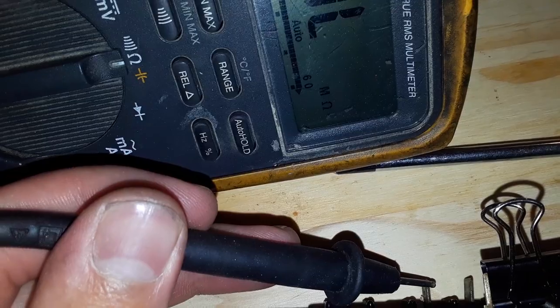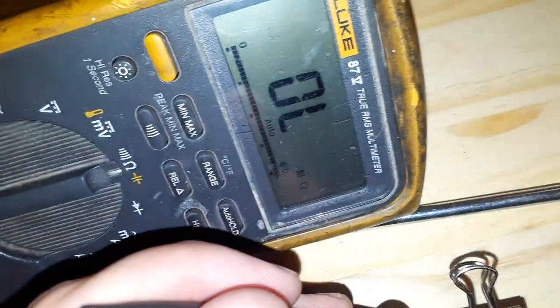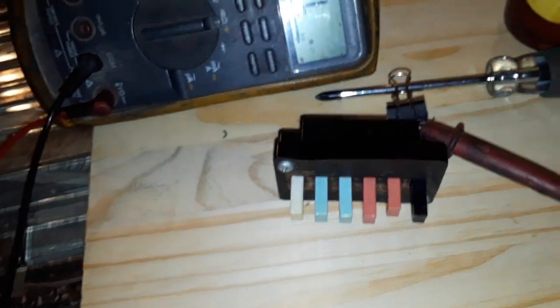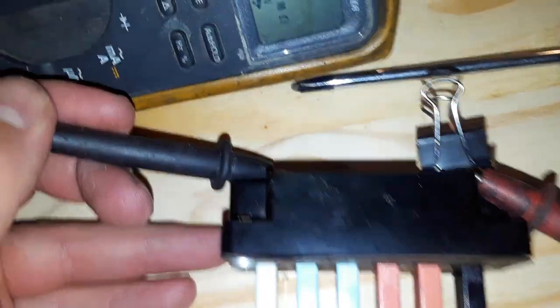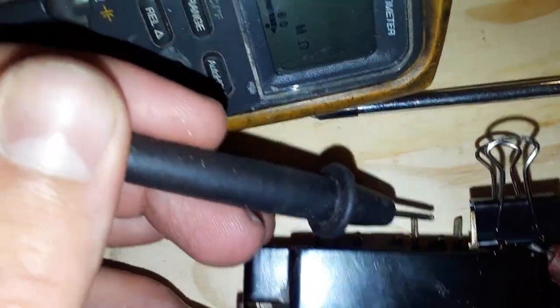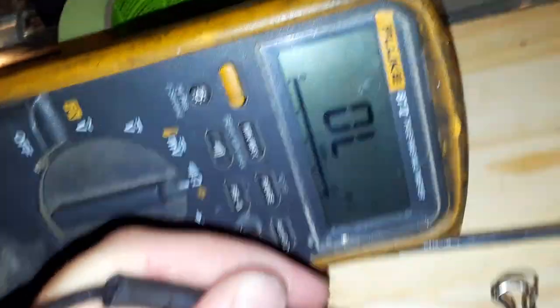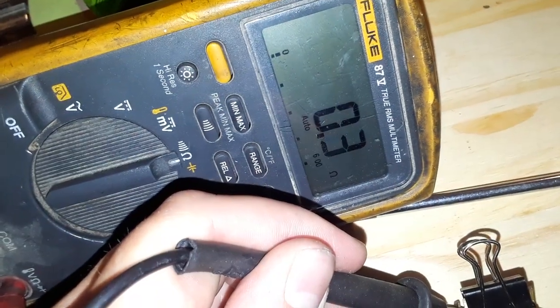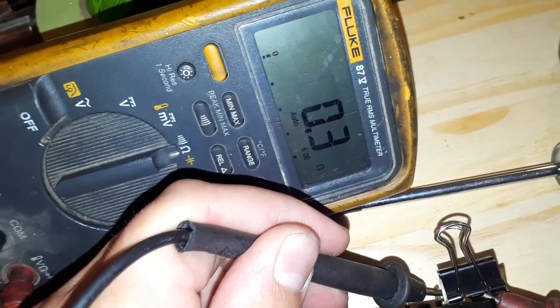So I should have no continuity on the compressor — it's off. And neither fan speed, high speed or low speed, should have anything. Okay so we're going to put it on high fan. If my calculations are correct the compressor will be off, which it is. Low speed should be off. And we should have roughly 0.2 ohms across the high speed contact because it's on high fan. And we do — 0.3 ohms. For guys who don't know, that's a dead short. That's exactly what you want.